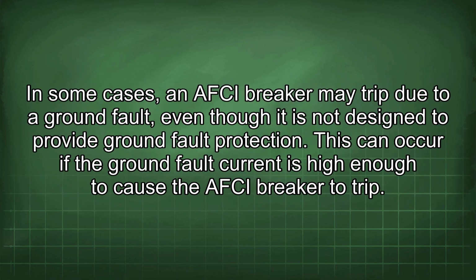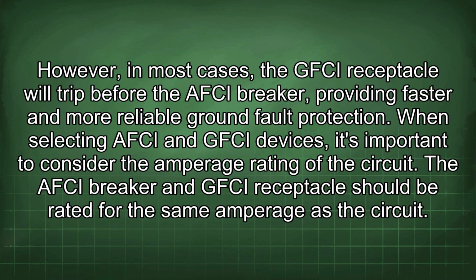In some cases, an AFCI breaker may trip due to a ground fault even though it is not designed to provide ground fault protection. This can occur if the ground fault current is high enough to cause the AFCI breaker to trip. However, in most cases, the GFCI receptacle will trip before the AFCI breaker, providing faster and more reliable ground fault protection.